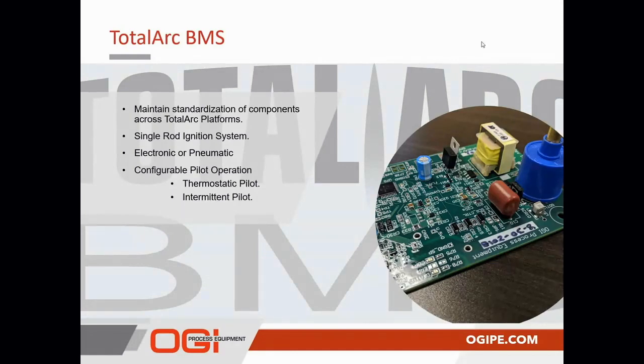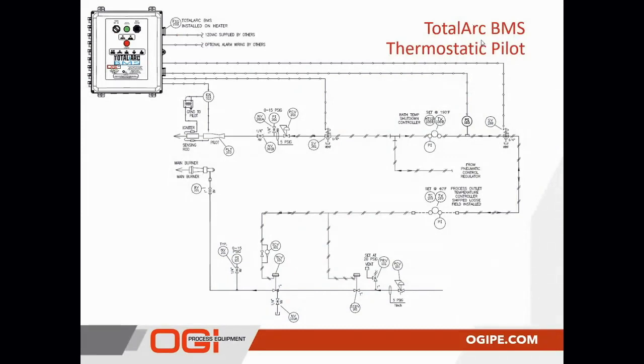For the TotalArc BMS thermostatic pilot, in the pneumatic configuration, the pneumatic safeties are being sensed and monitored by the BMS control system's pressure switch. When proven okay, the BMS will energize the pilot solenoid valve and light the pilot. After the pilot is lit, the main solenoid valve will be energized and the main burner will be cycled on and off depending on the process temperature controller that is downstream of that solenoid valve. The pilot will remain on as long as the pneumatic safeties are satisfied.